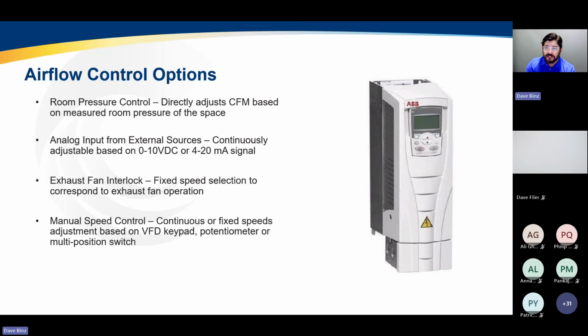So you mentioned earlier the challenge with industrial manufacturing is that this ventilation load may be highly variable. This application could go from 100,000 CFM of exhaust to 400,000 CFM of exhaust as lines turn on and off, or as the indoor operations change hour to hour. And so this is where airflow and variable volume makeup air applications become highly advantageous. And we've been doing variable volume direct-fired makeup air for over 25 years. We were some of the pioneers of actually being able to turn down airflow and modulate direct-fired heat in a very low airflow and low heat application. So we've been doing this for a long time.